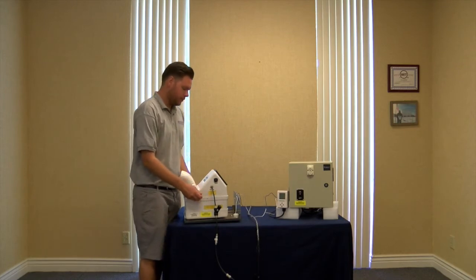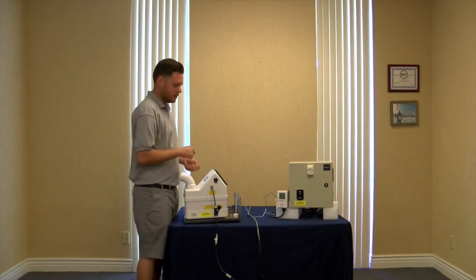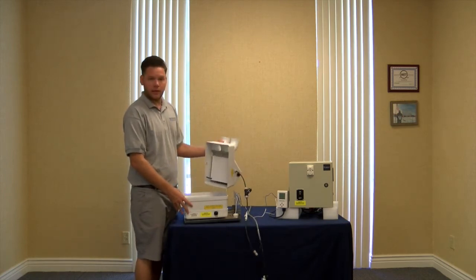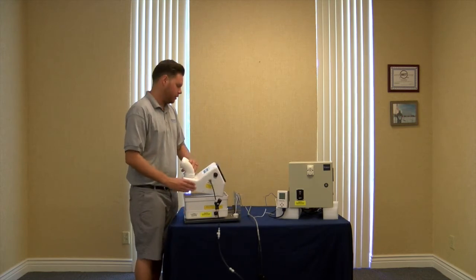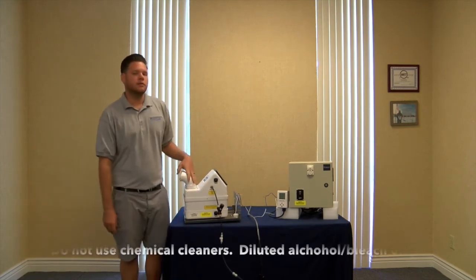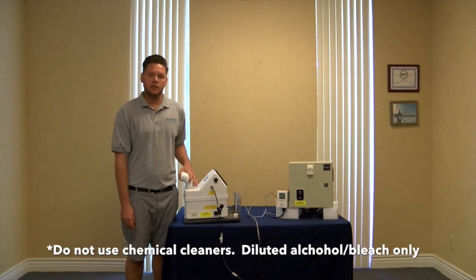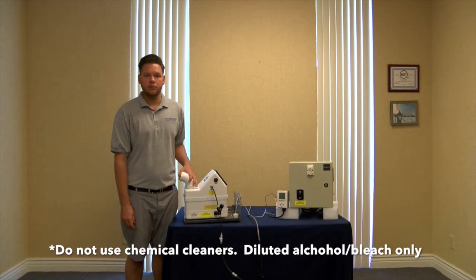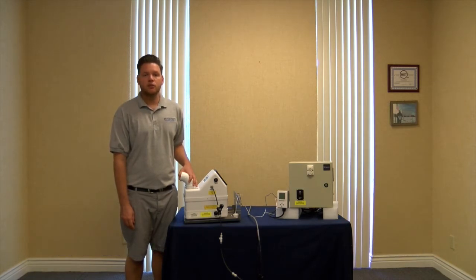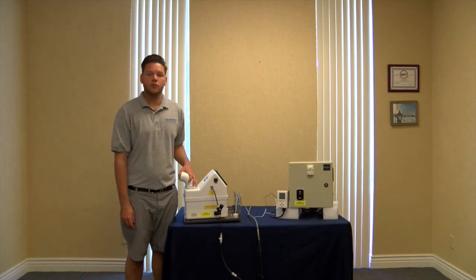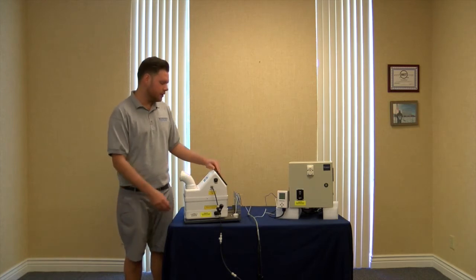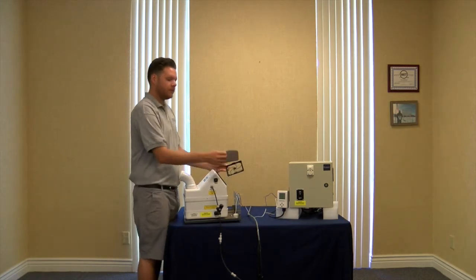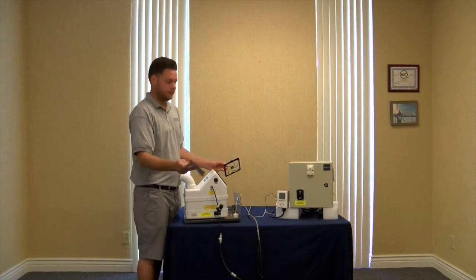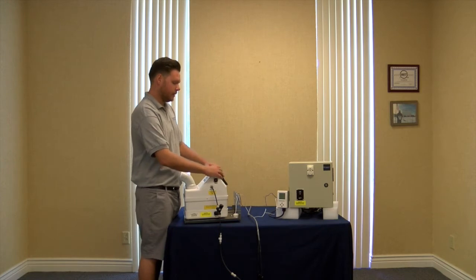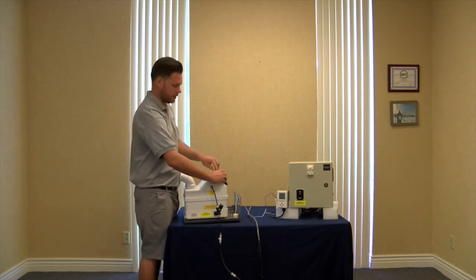Then simply remove the set screws on the outside of the humidifier to gain access to your water pan. To clean your water pan, you want to make sure that you don't use any finishing agents in your cleaner. Simply use a diluted bleach and wipe out the unit. Do not scrape or scratch at the transducers, because you will ruin the transducer crystallized disc. Also be sure to clean your fan filter by simply removing it off the back and rinsing it with water, making sure it is clean and doesn't restrict airflow.